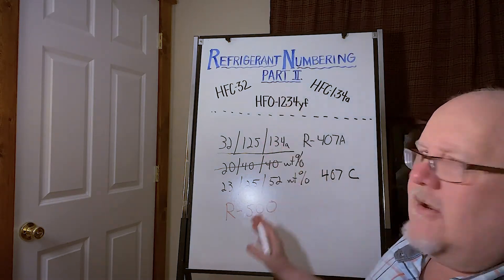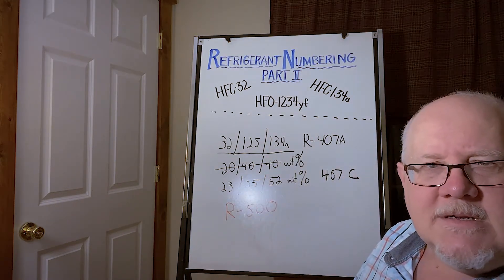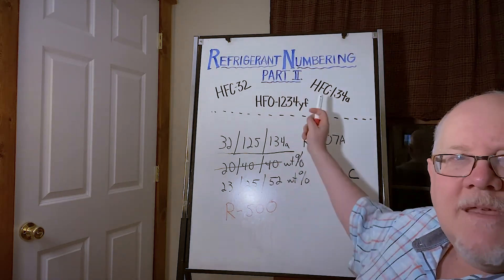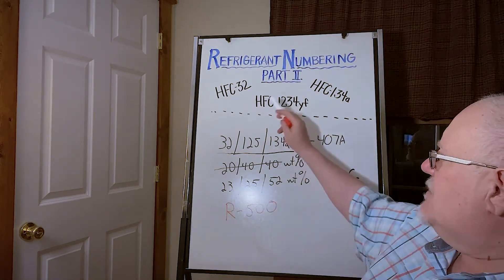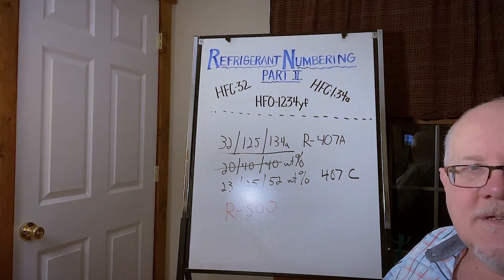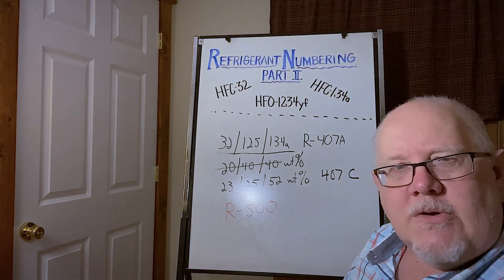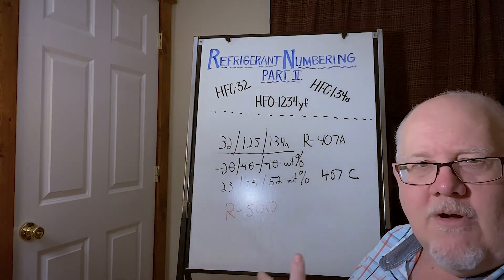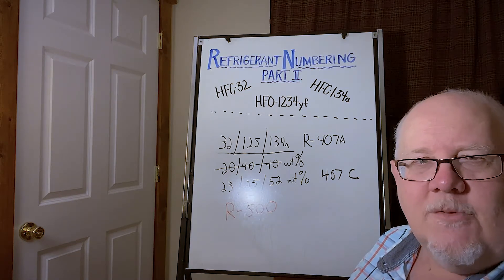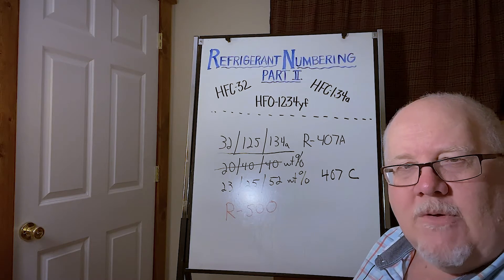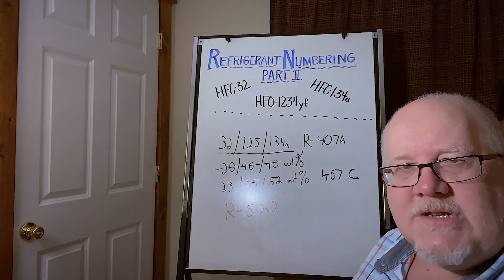And there's a lot of other properties that come into play when you start talking about the performance of these. But I just wanted to be clear on the naming and numbering system. Part one video covers how we get to the basic molecules. And then once we start building formulas, we start adding sequentially to the series of numbers. If it's a brand new combination of new constituents, it gets a new 400 series number. Unless it's an azeotrope, it'll get a 500 series number.